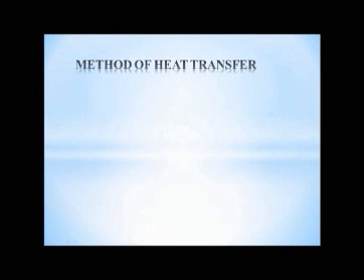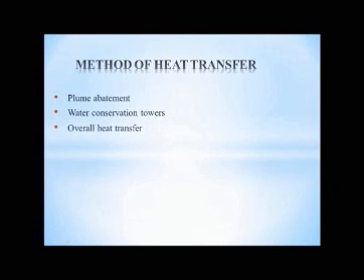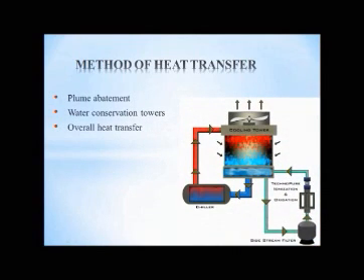Method of heat transfer: plume abatement, water conservation towers, overall heat transfer. All these cooling towers that we have described in our presentation are evaporative type towers, in that they derive their primary cooling effect from the evaporation that takes place when air and water are brought into direct contact. At the other end of the spectrum is the dry tower, where by full utilization of dry surface coil sections, no direct contact occurs between air and water.